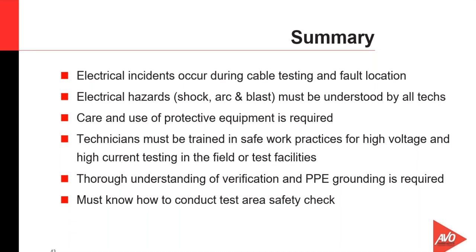So not only are you connecting it to a system out there that was energized and was an integral part of an operating power distribution system, we're actually simulating line currents and line voltages and things of that nature, which again puts us in a mode of being associated with live parts. The hazards of shock, arc, and blast need to be understood by anyone that works in the electrical industry. Being able to identify the risk associated with it and how to mitigate it with protective measures such as PPE and/or procedures is one reason why JHAs are so important.